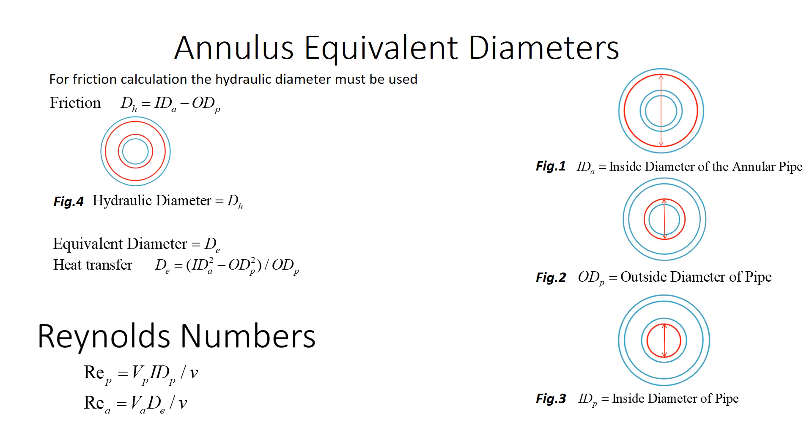For friction factor calculations, we must first find the hydraulic diameter, which is the inside diameter of the annular pipe minus the outside diameter of the inner pipe. For heat transfer calculations, the equivalent diameter must be used. The equivalent diameter equals the inside diameter of the annular pipe squared minus the outside diameter of the inner pipe squared divided by the outside diameter of the inner pipe.